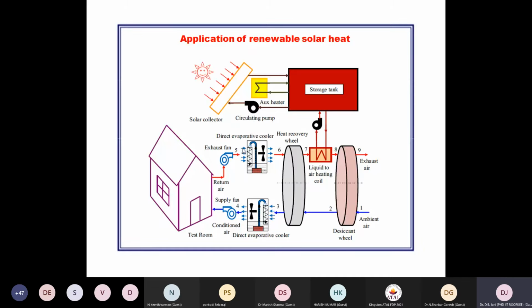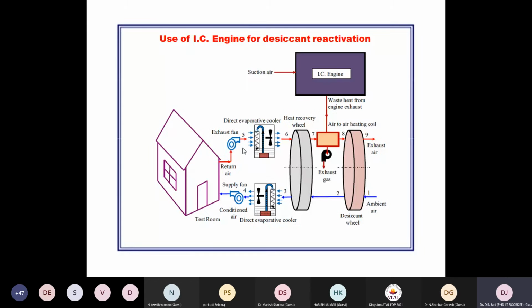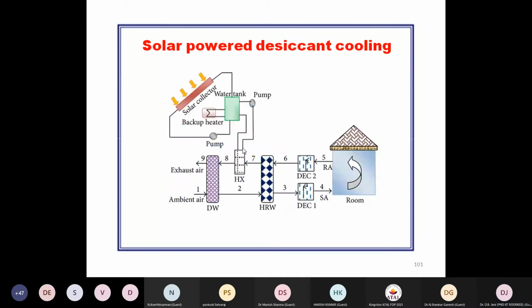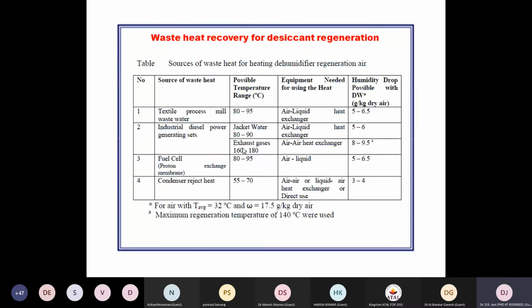Sometimes solar heat may be used, with a liquid-to-air heating coil incorporated for the purpose of dehumidifying. IC engine waste heat, diesel generator set waste heat, etc., may be used in some applications. So this is a typical range of waste heat available in different kinds of applications, along with the humidity drop within some range and the achievable regeneration temperature range, to be compared for the different applications.